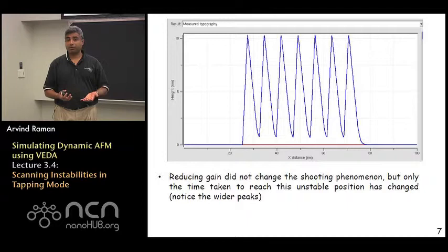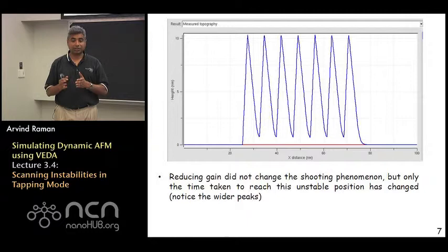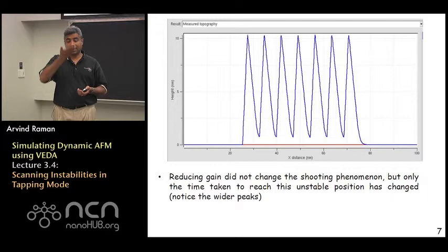The z controller is still moving up and down by several nanometers. What has changed is the frequency of these up and down motions, but the fact that it goes up and down, not knowing where to sit, basically still persists even when your integral gain has been reduced.